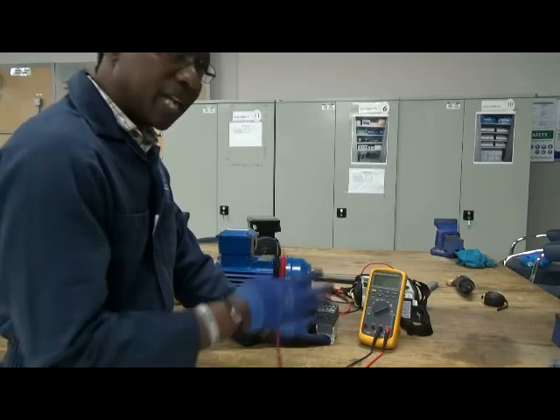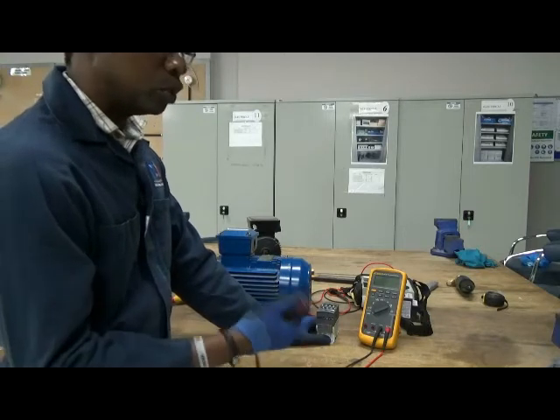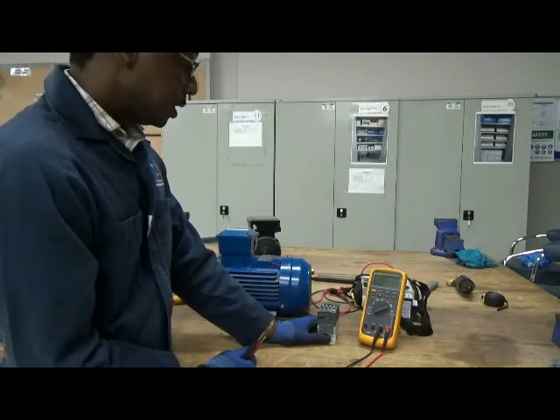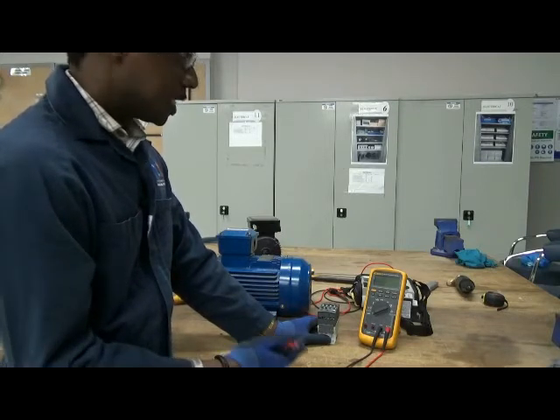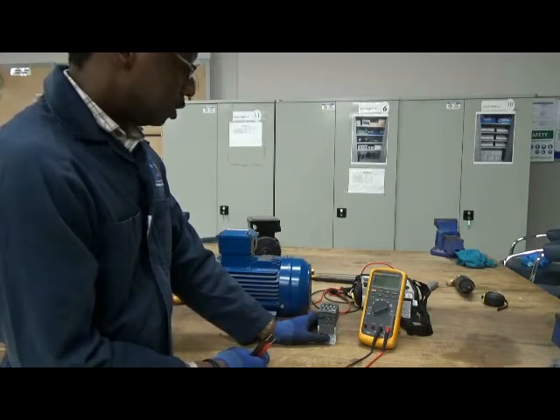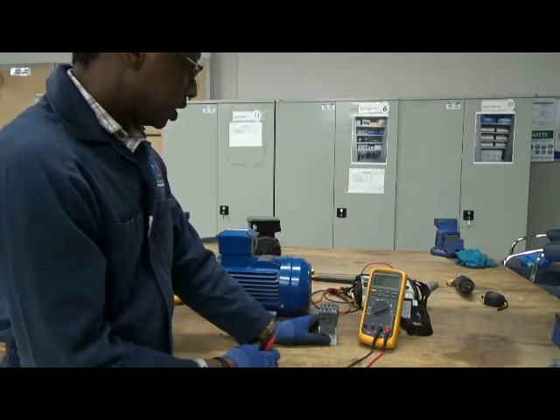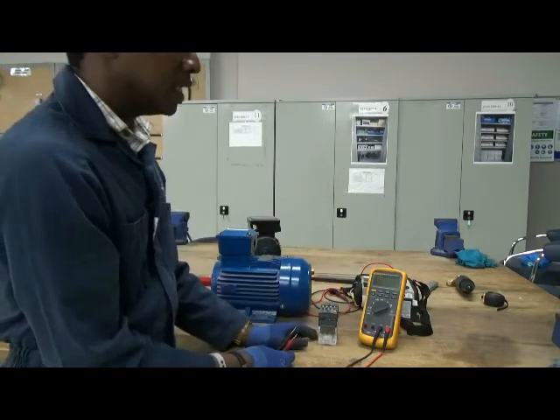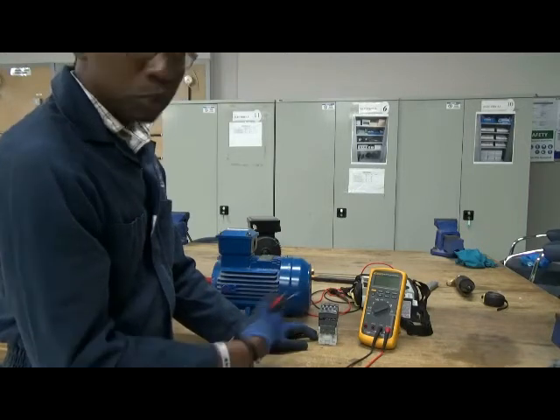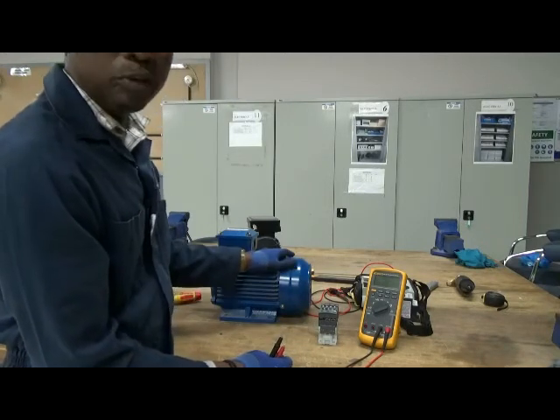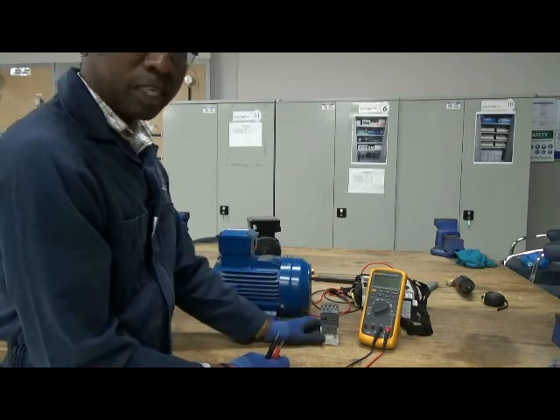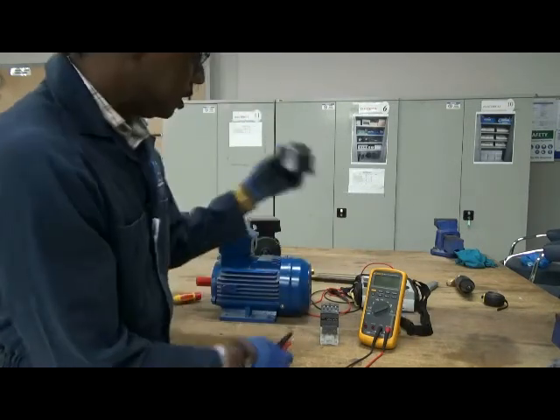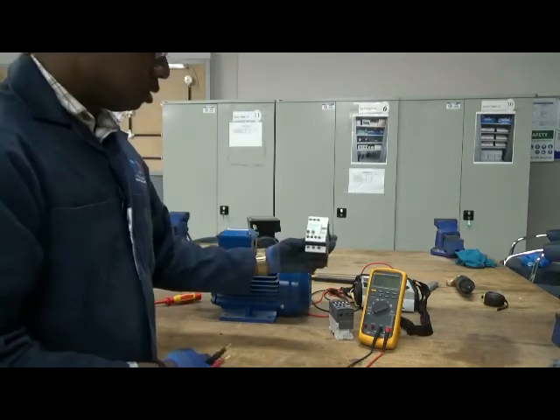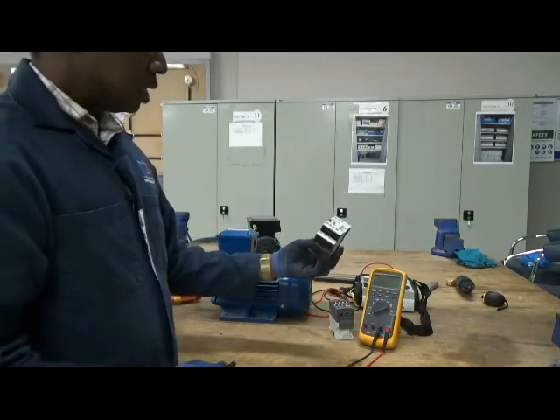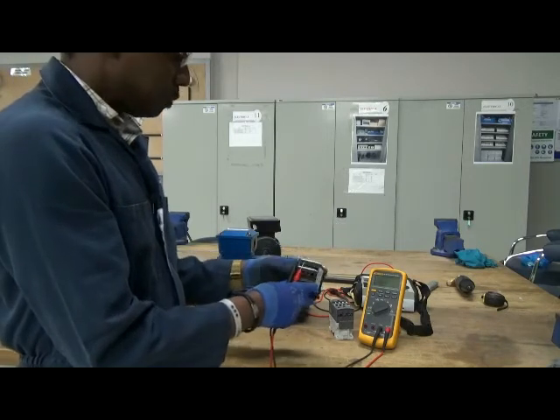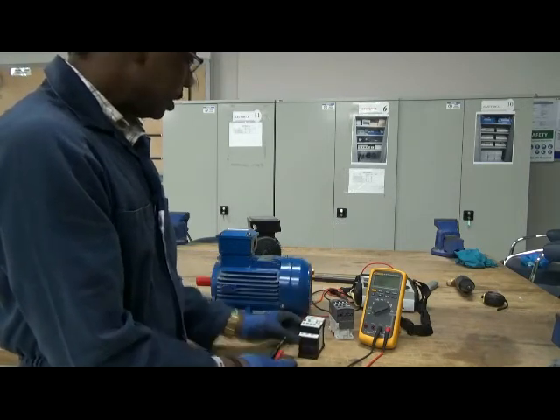and off. Of course, there are other components involved, like your push stop and start buttons, and so on and so forth. Depending on the control, how it was designed, in most cases the control circuit is made up of numerous components and protection devices like control fuses. You also sometimes have main fuses to protect the motor windings against short circuits. But of importance is this other small component here, which we call an overload. An overload relay is for protection against overloads on the motor.